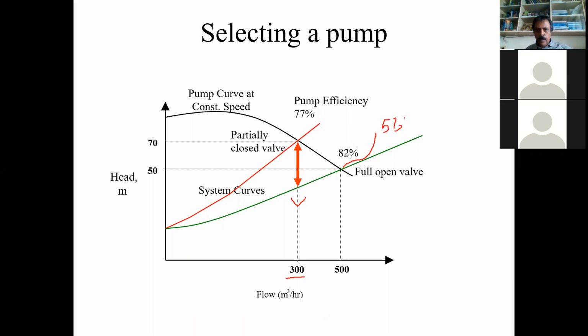Okay. Now we have throttled the pump. The efficiency has come down from 82 to 77. What will be the power here? As we measure the power, we find it is only 45 kilowatt. So what has happened? By throttling, we have reduced the power consumption. So can we take it as an energy conservation measure? Have we saved energy by throttling?